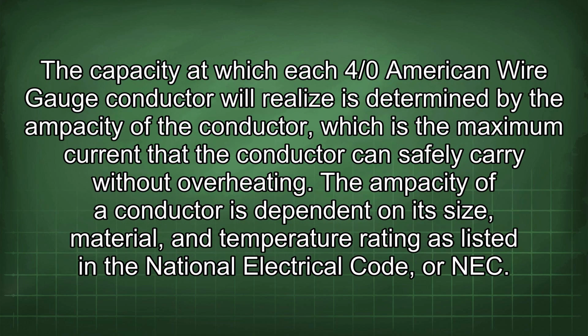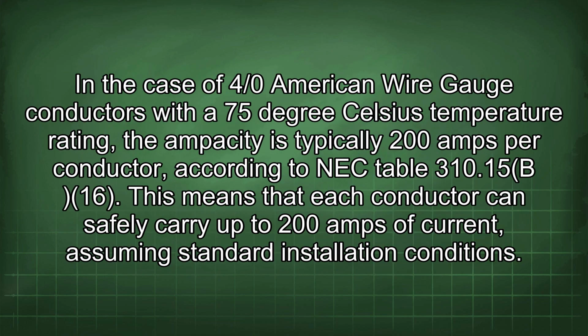The capacity at which each 4/0 American wire gauge conductor will operate is determined by the ampacity of the conductor, which is the maximum current that the conductor can safely carry without overheating. The ampacity of a conductor is dependent on its size, material, and temperature rating as listed in the National Electrical Code, or NEC. In the case of 4/0 American wire gauge conductors with a 75°C temperature rating, the ampacity is typically 200 amps per conductor, according to NEC Table 310.15(B)(16). This means that each conductor can safely carry up to 200 amps of current, assuming standard installation conditions.